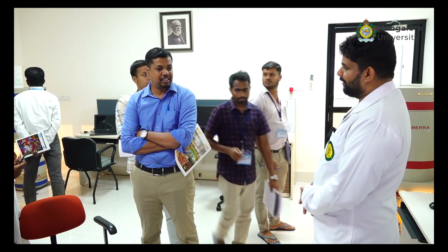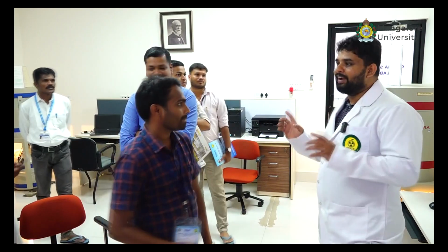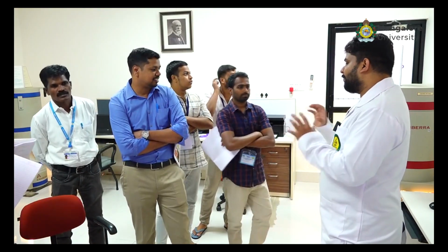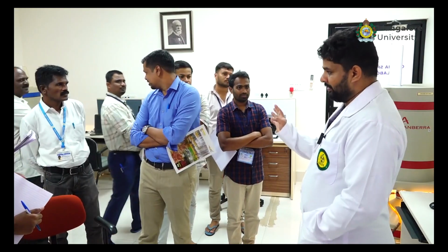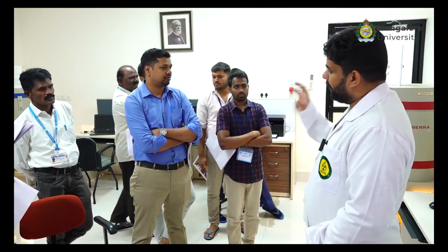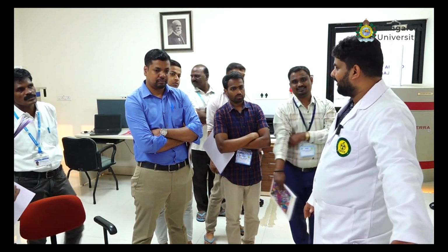One HPGe. Wrong. It's the other way around. So we basically have 3 HPGe and 1 sodium iodide. The easiest way to identify an HPGe is that it will always have a liquid nitrogen cylinder with it. In most cases, unless it is a very advanced HPGe with electronic cooling, but again, it will have something below. Sodium iodide will not have anything.